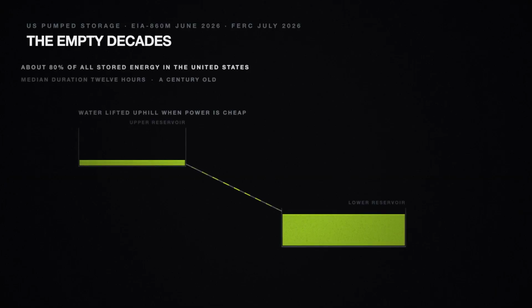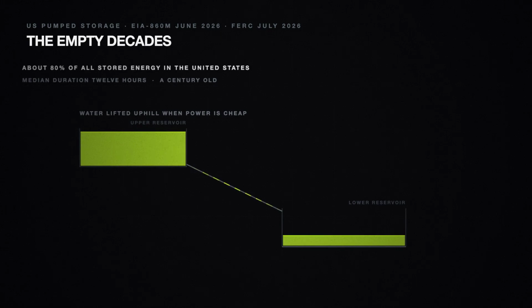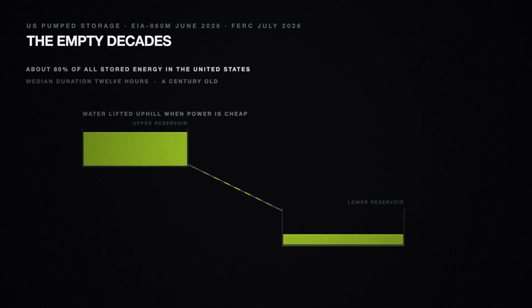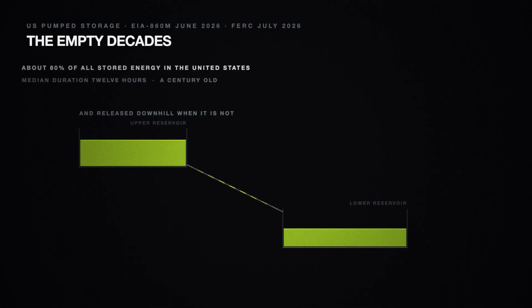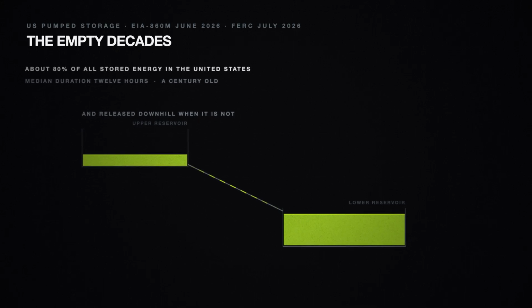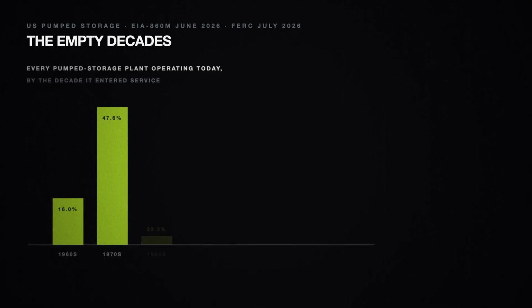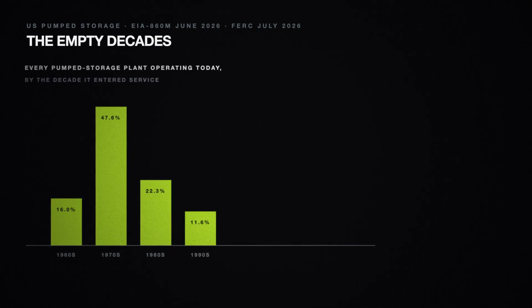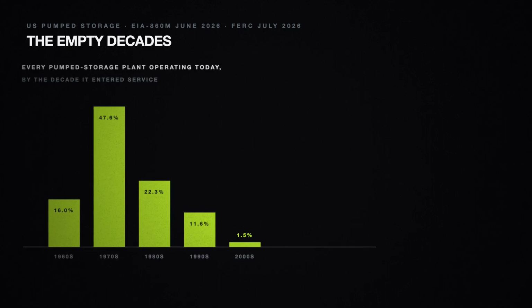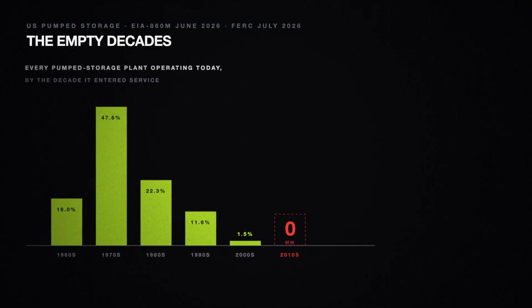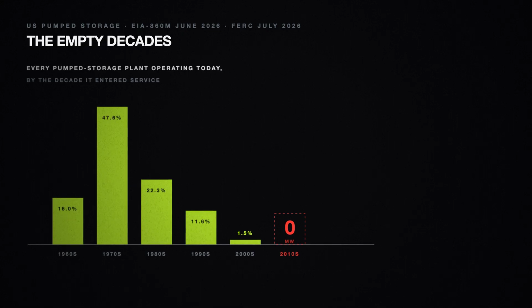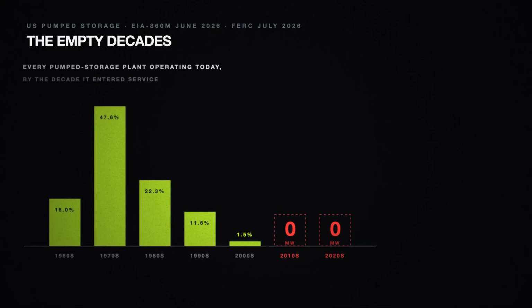There is a technology that does what batteries cannot. It holds about 80% of all the stored energy in the United States at a median duration of 12 hours. Pumped storage, water lifted uphill when power is cheap, released downhill when it is not. A century-old, unglamorous, and by far the largest battery America has. Here is when it was built. 16% in the 1960s, 48% in the 1970s, 22% in the 80s. Almost 86% of the entire national fleet entered service between 1960 and 1989. In the 2010s, the United States added 0 megawatts of pumped storage. In the 2020s, so far 0.